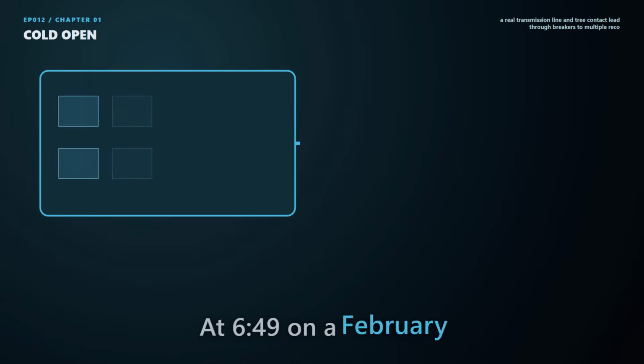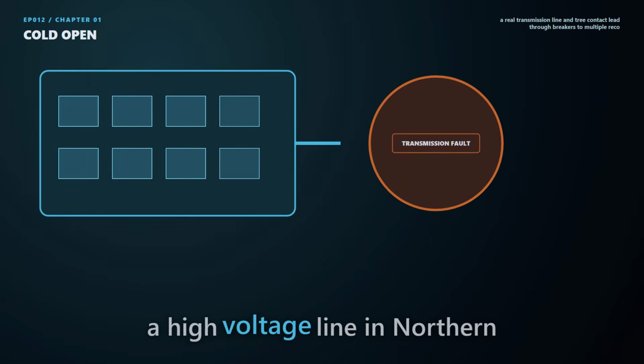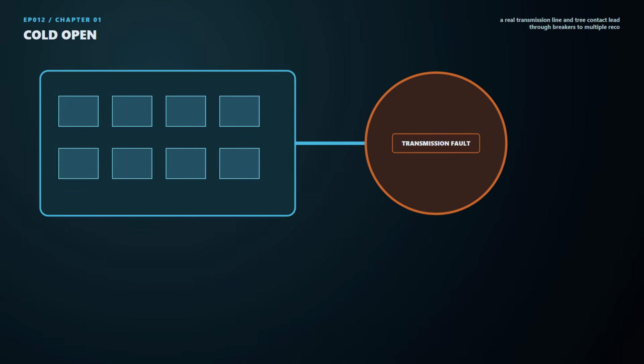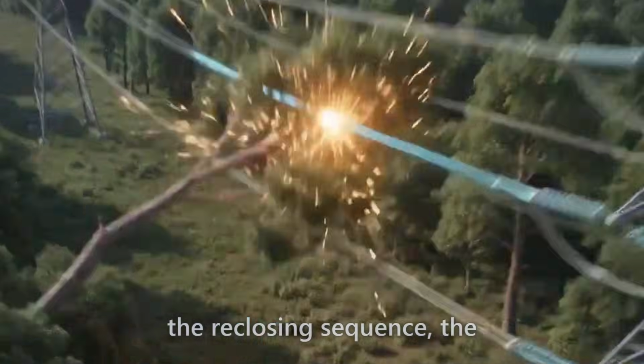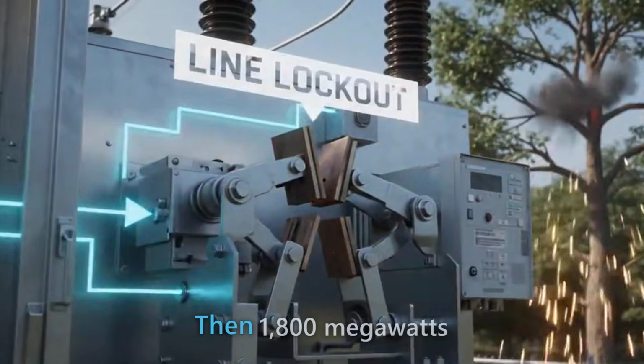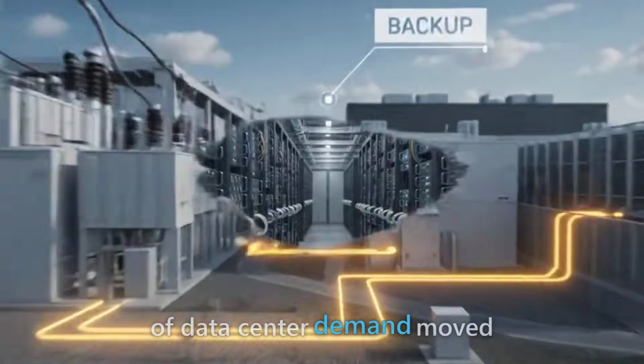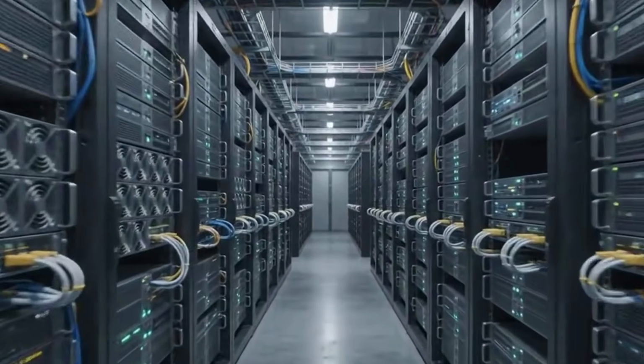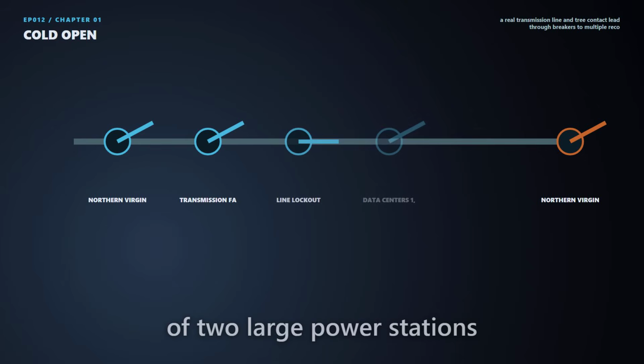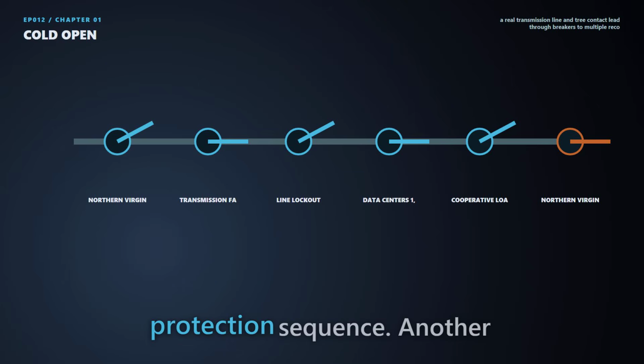At 6:49 on a February morning, a tree touched a high-voltage line in Northern Virginia. Protection cleared the fault current. After the reclosing sequence, the line locked out. Then 1,800 megawatts of data center demand moved off Dominion Energy's system. That is roughly the output of 2 large power stations changing sides within one protection sequence.